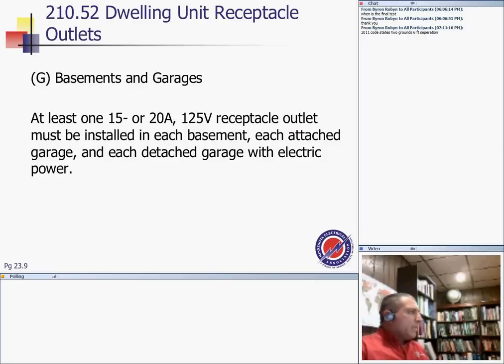The basement, at least one 15 or 20 amp receptacle outlet installed in each garage, or each detached garage with electric, or basement. So if the detached garage is powered, then you have to have a receptacle in it. Attached garage, you must have at least one receptacle, GFCI, weatherproof, tamper resistant.